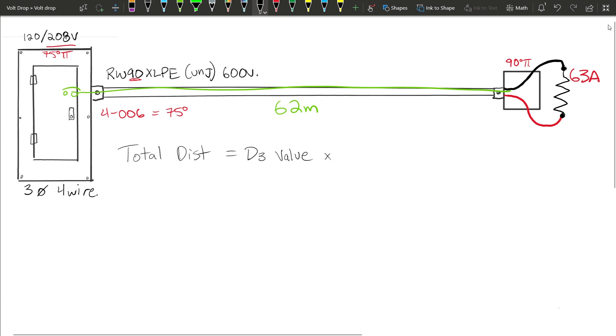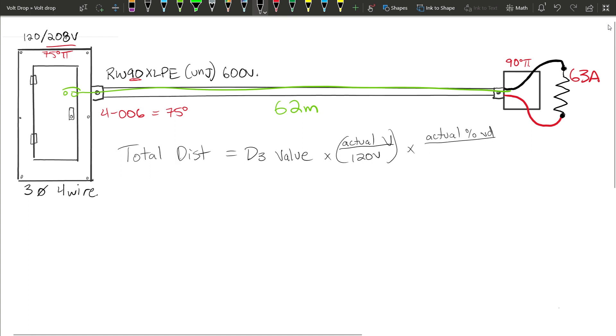We'll start with the formula we built last time. Total distance equals the D3 value multiplied by factors that D3 is built off of. Table D3 is built off of 120 volts at a one percent volt drop with two conductors, so anything different from that we have to apply a ratio: actual voltage divided by 120 volts, multiplied by actual percent volt drop compared to one percent.